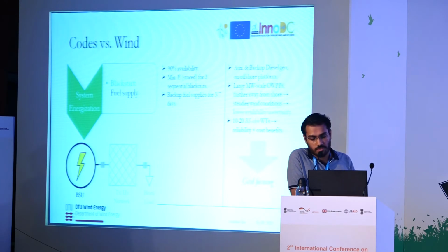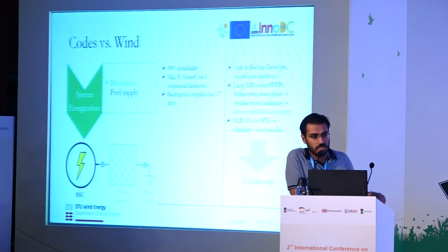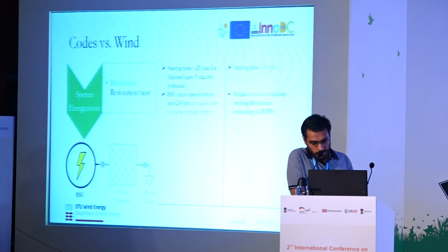And then, of course, if you have, let's say, 20 Blackstartable wind turbines out of 400, maybe on the edge of the wind plant, that can provide some extra reliability or cost benefits and also help save the insurance costs for diesel, for example. As far as startup time is concerned, wind turbines are really fast in ramping up, given they have an auxiliary supply or a battery storage. For example, GE has an internal battery now in one of its wind turbines.